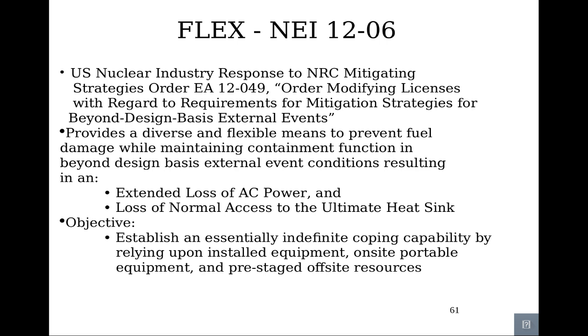In addition to the B.5.b requirements, the Nuclear Energy Institute Recommendation 12-06 institutes requirements for FLEX equipment, which provide a diverse and flexible means to prevent fuel damage while maintaining containment function in beyond design basis external event conditions, resulting in extended loss of AC power and loss of normal access to the ultimate heat sink. The objective was to establish an essentially indefinite coping capability by relying upon installed equipment, on-site portable equipment, and pre-staged off-site resources.